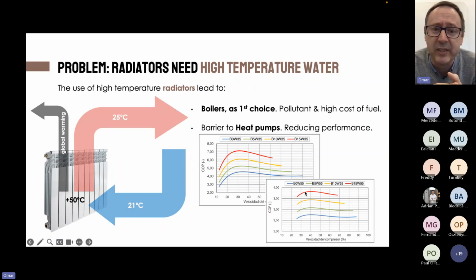Yes, of course they can operate at very high temperatures, but in the graphs on the top, with a low temperature differential, they have twice the performance than when we are forced to work with water production temperatures above 50 Celsius, where the COP really gets reduced. And this is important because if we don't want to just be forced by law to replace the boilers with the heat pump, we have to try to be as competitive as possible, to get the highest possible COP in order to reduce the real cost of the thermal energy we are supplying, and get a return of investment as short as possible.